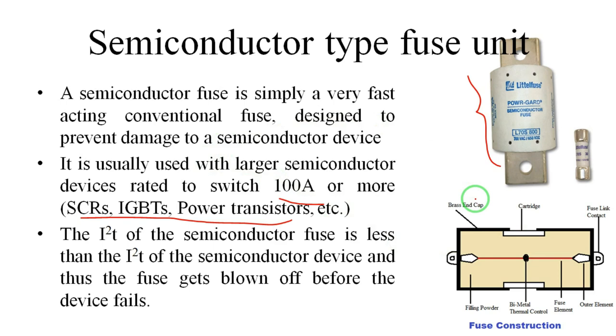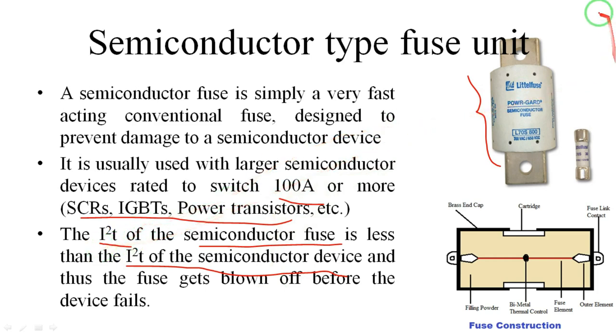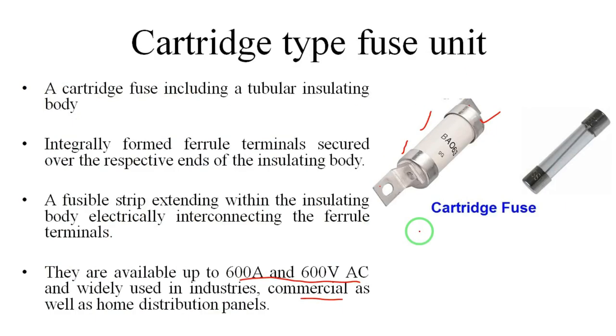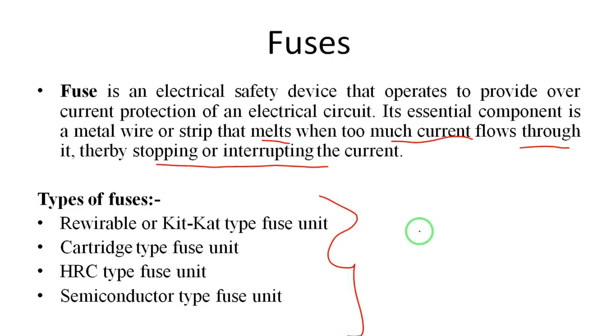The semiconductor fuse is a very fast-acting conventional fuse designed to prevent damage to semiconductor devices. This fuse has a lower I²t value compared to the semiconductor device's I²t value. When high current flows toward the semiconductor device, the semiconductor fuse — connected before the device — melts first because of its lower I²t value. The fuse blows before the device fails, thereby protecting the semiconductor device. This concludes the discussion on the four types of fuses.